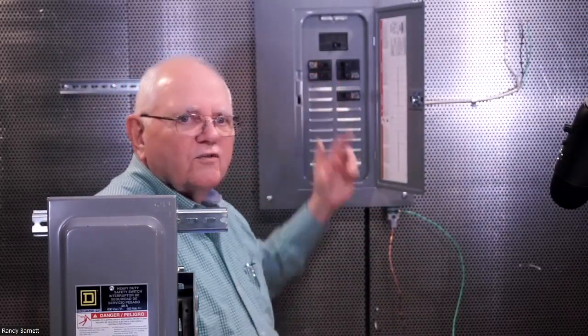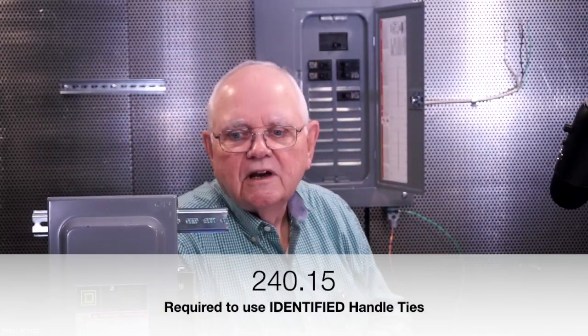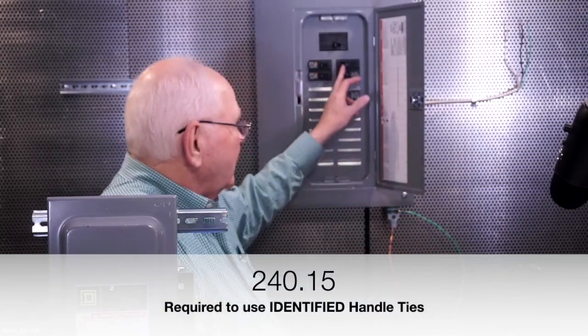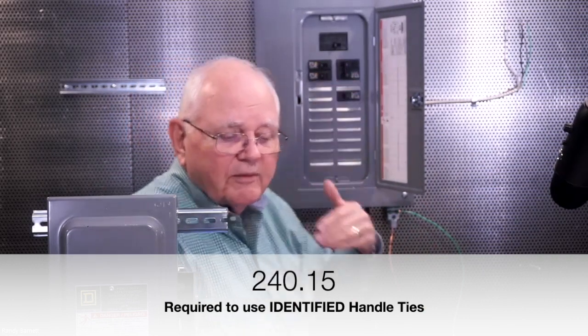And in Article 240, it says I have to use identified handle ties. Now, I actually have one over here on the right. It's pretty hard for you to see from that distance, but it is two separate molded case breakers tied together with an identified handle tie. So we can certainly use our molded case breakers, very often used for disconnecting means, and different types of switches and so on.